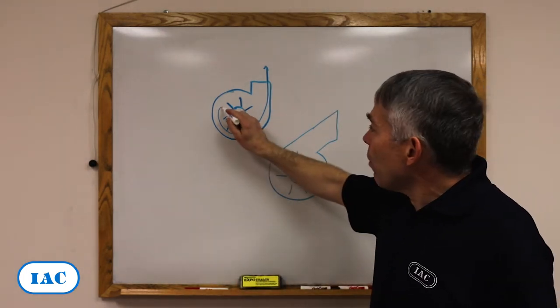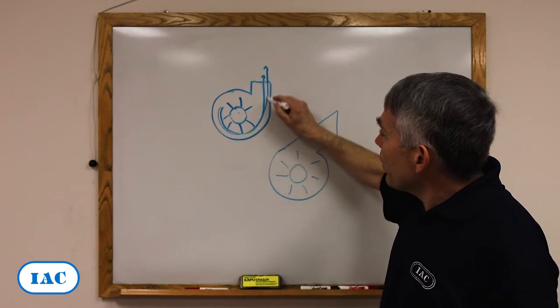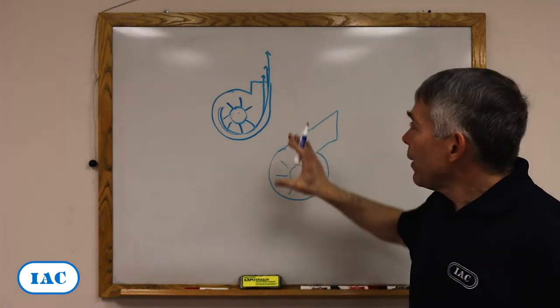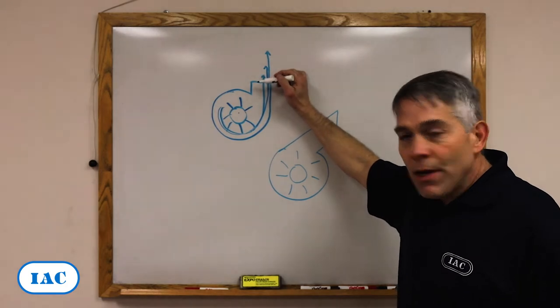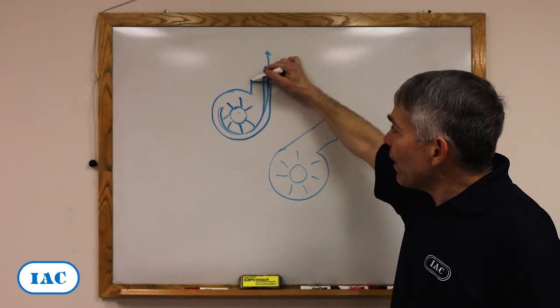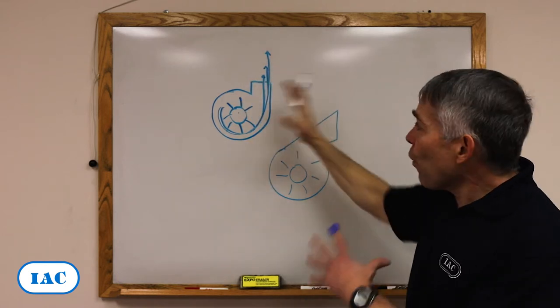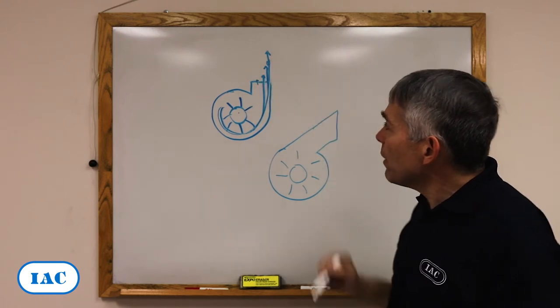Just picturing what's going on here, we talked about fan rotation, but picture what's going on. Just by looking at what I just drew, tells you that there's something called velocity profile on the outlet of this fan. Velocity profile means that the velocity of the air at the far edge is a lot more than the air coming here in the middle.